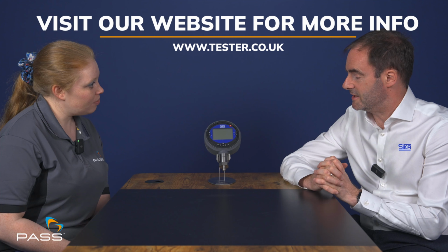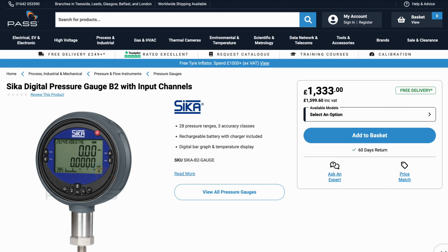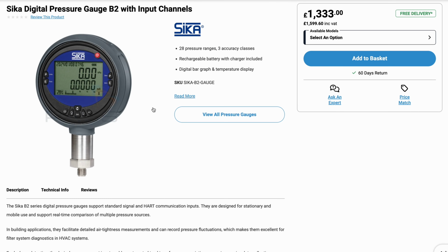Today we're talking about Sika's B2 digital pressure gauges. But before we get into the details of these instruments, please could you tell us for whom and what they are designed for? Yeah, no problem. The B2 pressure gauge is a calibration type pressure gauge. It's ideal for engineers or service engineers to take on site and calibrate locally using a pressure pump or connecting to the customer's system as well.